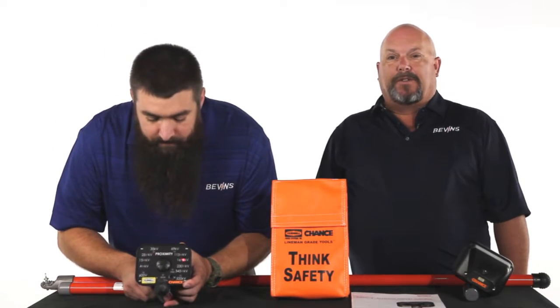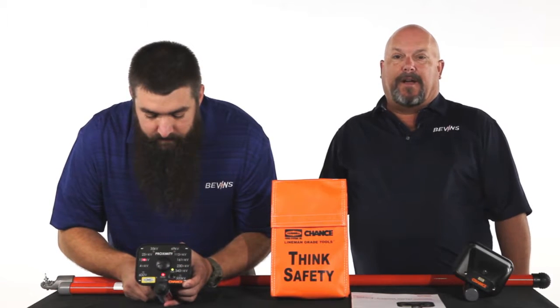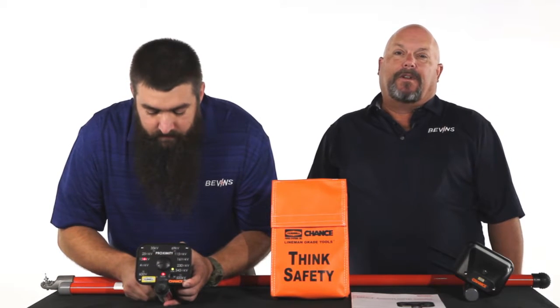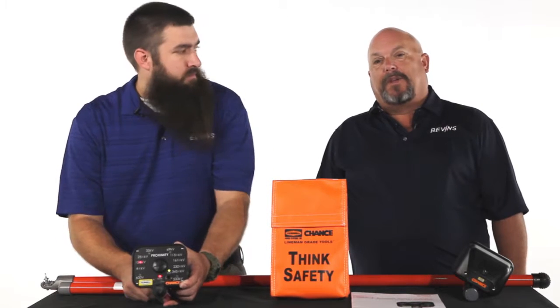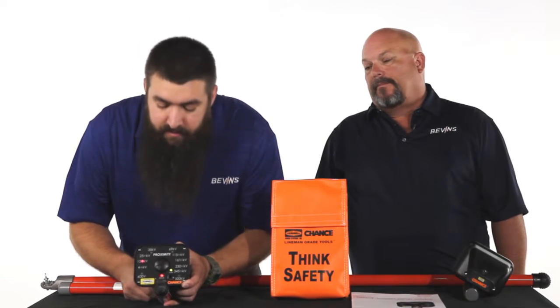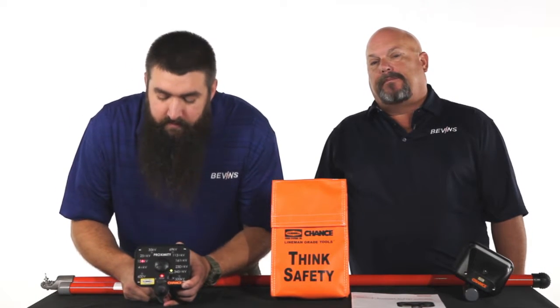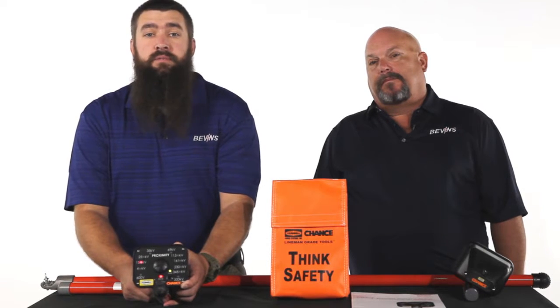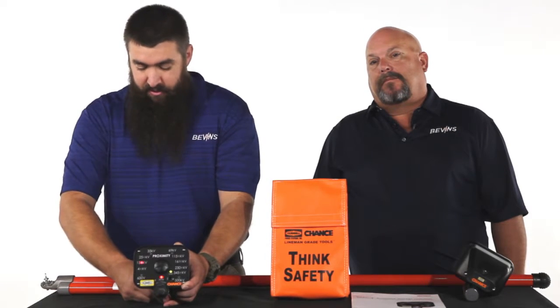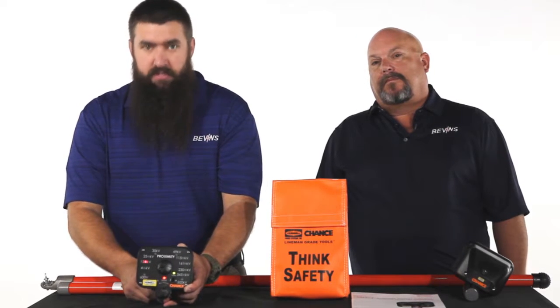Now, the reason that we use a 9-volt battery is because a 9-volt battery doesn't have enough energy source to push any breaks that might be in the unit. And as you can see on the front of the unit, we've got a 15 kV indication, which is just as it should be. An operable unit will indicate voltage when connected to the external tester.